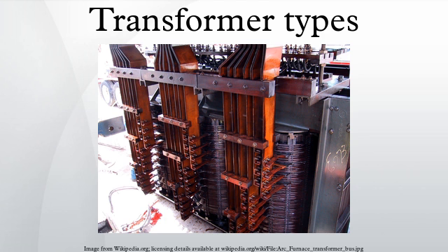There are three primary types of voltage transformers, or VTs: electromagnetic, capacitor, and optical. The electromagnetic voltage transformer is a wire-wound transformer. The capacitor voltage transformer uses a capacitance potential divider and is used at higher voltages due to a lower cost than an electromagnetic VT. An optical voltage transformer exploits the electrical properties of optical materials. Measurement of high voltages is possible by the potential transformers. Combined instrument transformer.